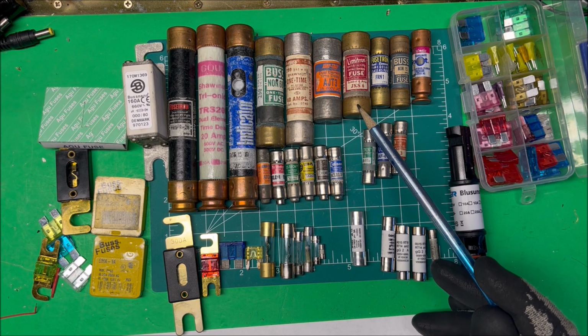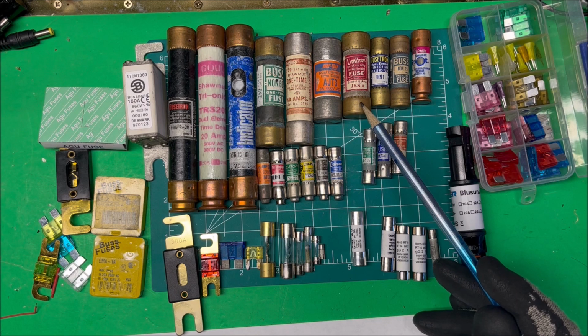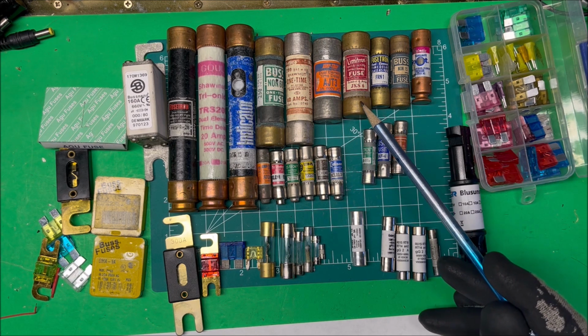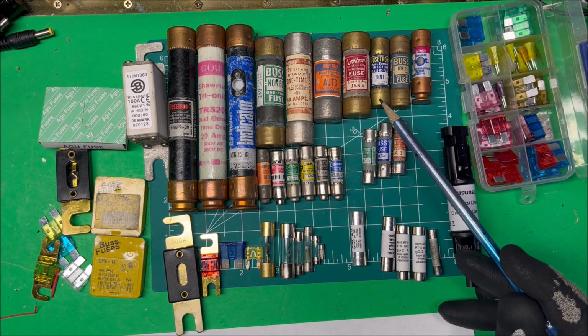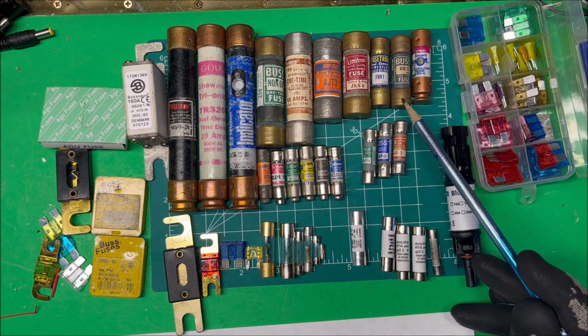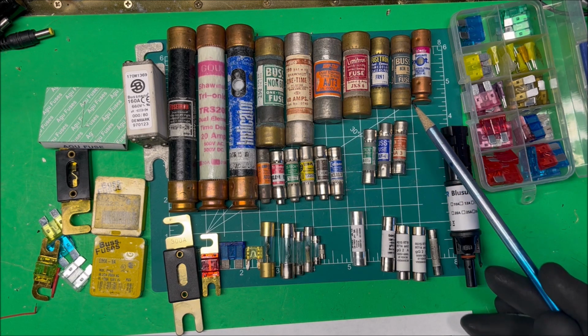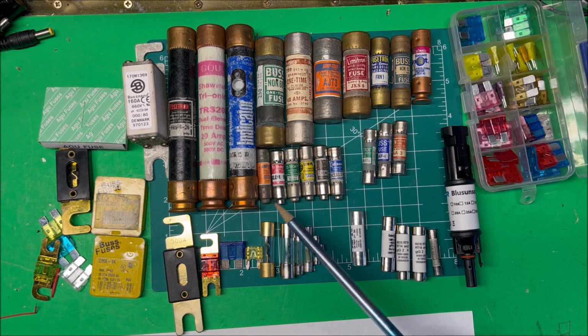and this one here is good for an AIC rating of 100,000 amps. Huge. And then this is a time delay fuse for motor starting. This is 240 volt for 240 volt motors.